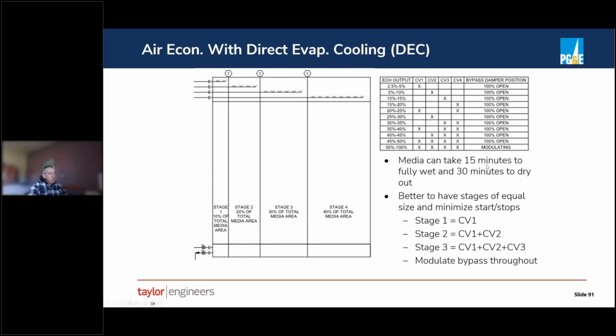Okay. So what we found in our experience is to have stages of equal size instead of 4 stages of different sizes. We'll basically split it into just 2 or 3 equally sized stages. And then once you bring on a stage, you kind of keep it on because it takes a long time to get going and a long time to stop. So you basically just sort of stack them on top of each other. So we would have control valve 1 turn on, then we would turn on valve 2, then we would turn on valve 3. And as I said, we would modulate the bypass throughout. And that sort of gives you the modulating control that you really don't get with the step control of the individual stages. I think I'm going to pass this slide.